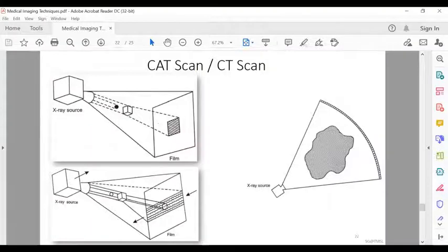So the X-ray source and the film move simultaneously in opposite direction. One plane appears stationary on the film and the small sphere lies on the same plane. But present day, as you can see on the right hand side, CT scanners use X-ray sources which provide fan beams and multiple detectors to simultaneously measure the density across a wide portion of the slice.